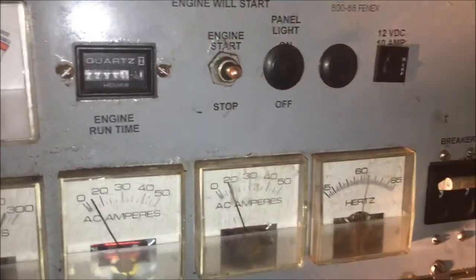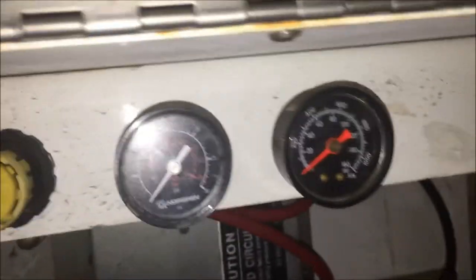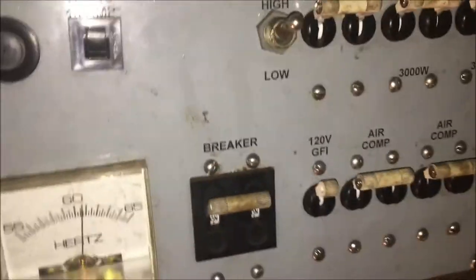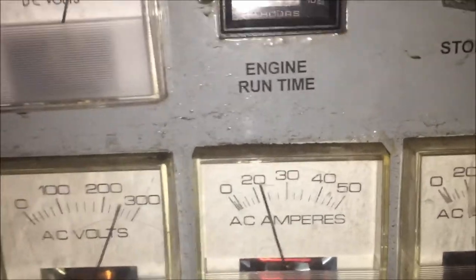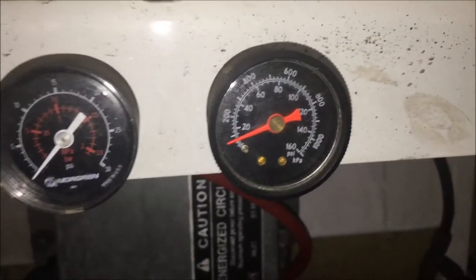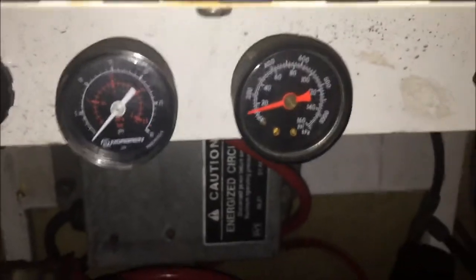Good — hear it now. We're going to fire up the compressor. Notice there's zero PSI. We're loading it — that's crazy. Now I've got both compressor heads working. We're going about pretty close to 50 amps, and you can watch the air pressure go up on the high pressure side. It's rolling good.